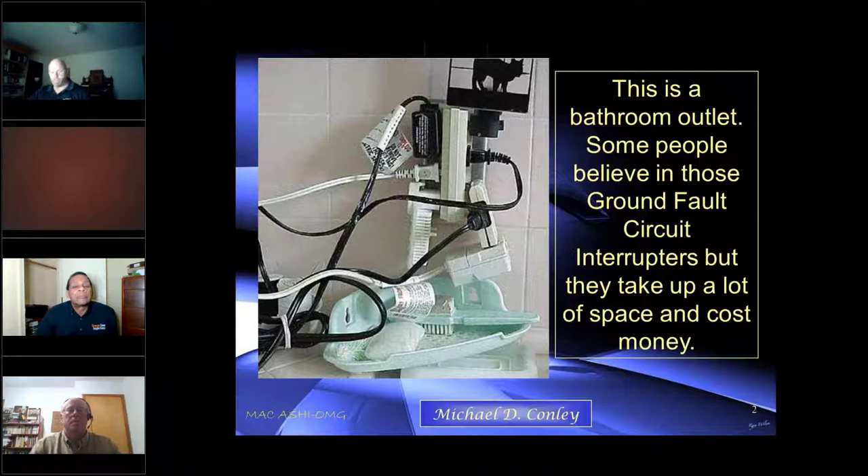There are restrictions on some of what I just said. If it's a bathroom circuit you can only do so much. If it's a kitchen countertop circuit, the kitchen is required to have two 20-amp independent circuits handling the countertop receptacles. But generally, if you've got a line circuit you can have as many receptacles as you want.